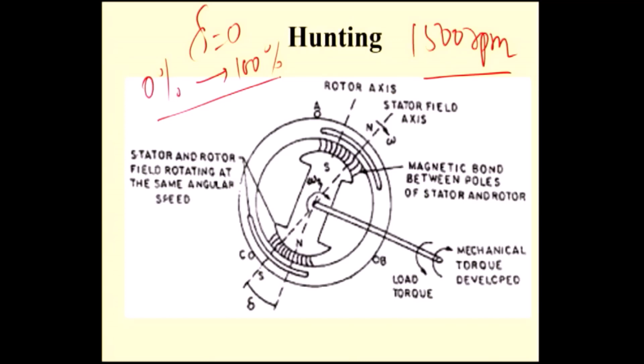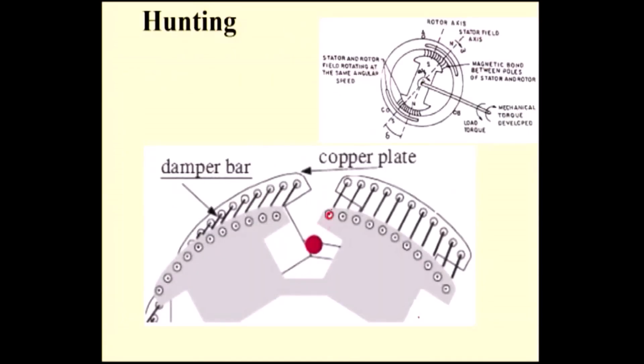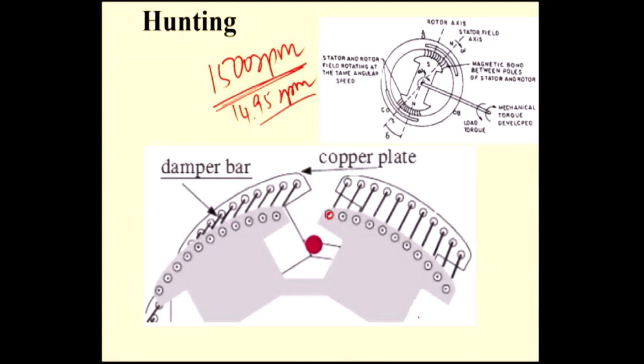At that case, what will happen? There is a damper winding. Whenever a conductor cuts the magnetic flux, EMF will be induced. The rotating magnetic field runs at constant speed — 1500 RPM. Because of the increase in load, the rotor speed slightly decreases, say to 1495 RPM. So there is a small speed difference between the rotating magnetic field and the rotor. Because of this speed difference, EMF will be induced in the damper winding. The damper winding is nothing but squirrel cage winding, placed in the pole face of the rotor.